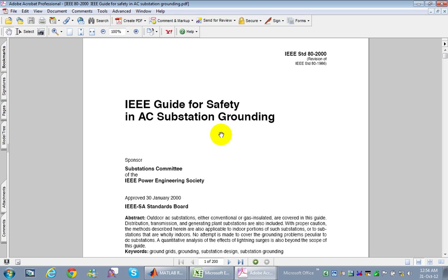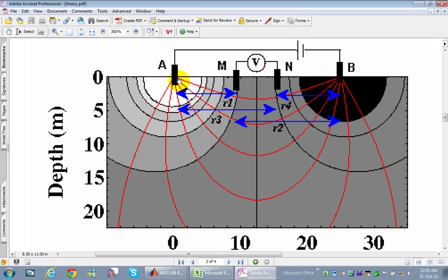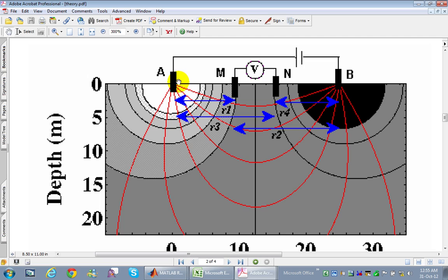The behavior of the earth when passing current through it will differ from area to area. The common method to measure soil resistivity is the four-electrode method, also called the Wenner method. There are many commercial devices used for this purpose. The basic concept involves inserting four rods into the substation land — the outer two electrodes, A and B, are used for injecting current.